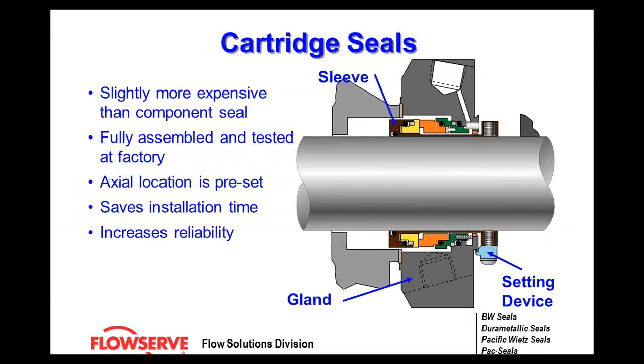How do you get around that? Simple — cartridge seal designs. A cartridge seal is a seal in a package, slightly more expensive because it includes a sleeve and a gland. They are all-in-one units, fully assembled and tested at the factory, with the axial location already preset. All you have to do is put it on the shaft, build the pump to its specs, tighten the seal gland to the desired torque settings, lock the sleeve to the shaft, remove the setting devices, and it's ready to go. This greatly saves on installation time, reduces mistakes, and greatly increases reliability.